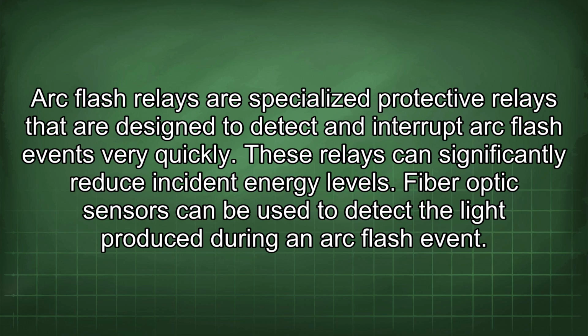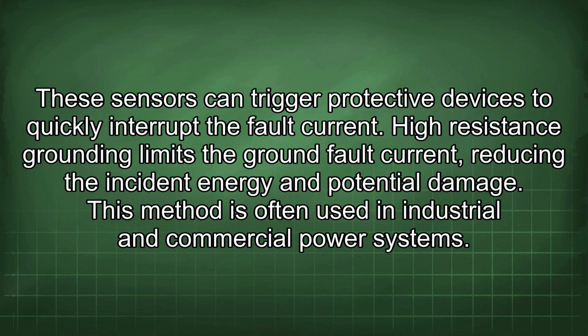Fiber optic sensors can be used to detect the light produced during an arc flash event. These sensors can trigger protective devices to quickly interrupt the fault current. High resistance grounding limits the ground fault current, reducing the incident energy and potential damage. This method is often used in industrial and commercial power systems.